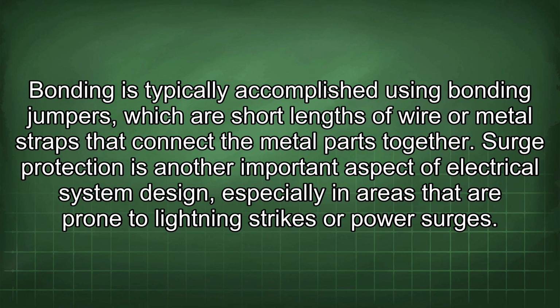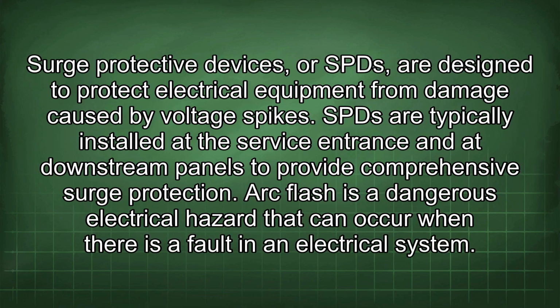Surge protection is another important aspect of electrical system design, especially in areas that are prone to lightning strikes or power surges. Surge protective devices, or SPDs, are designed to protect electrical equipment from damage caused by voltage spikes. SPDs are typically installed at the service entrance and at downstream panels to provide comprehensive surge protection.